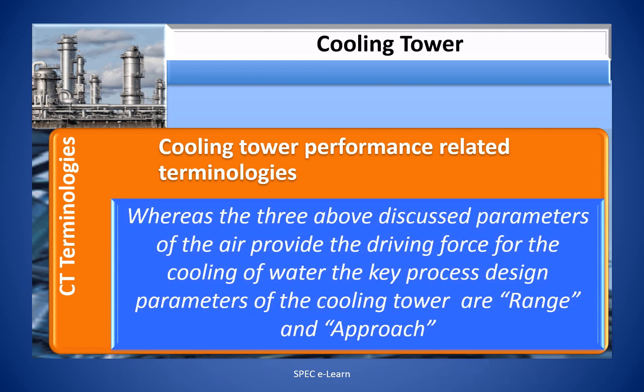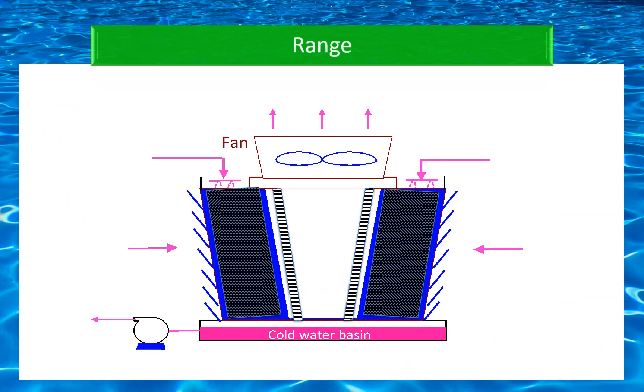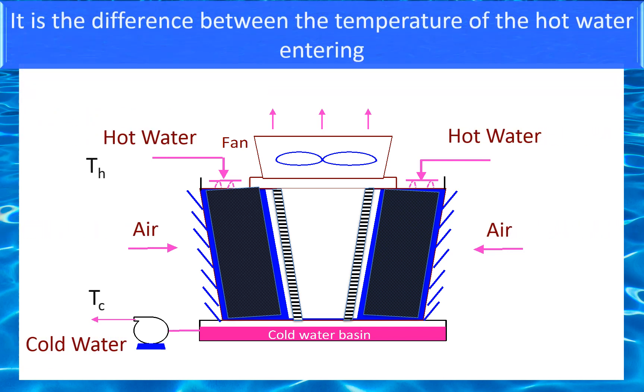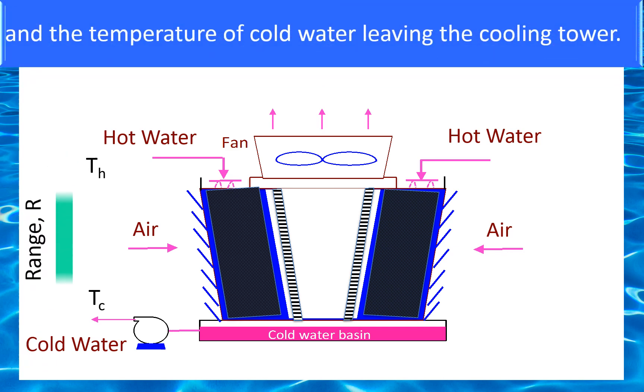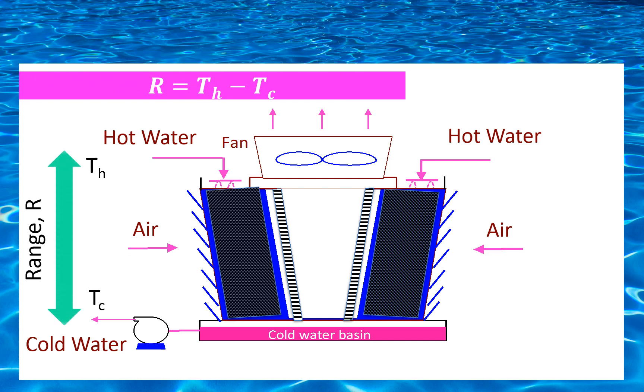Cooling tower performance related terminologies. The three air parameters provide the driving force for cooling of water. The key process design parameters are range and approach. Range is designated by the letter R — it is the difference between the temperature of hot water entering and the cold water leaving the cooling tower: R = TH − TC.